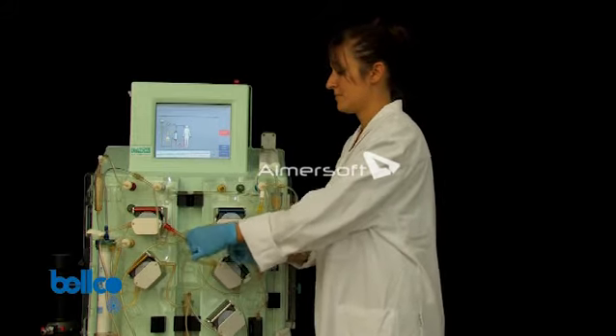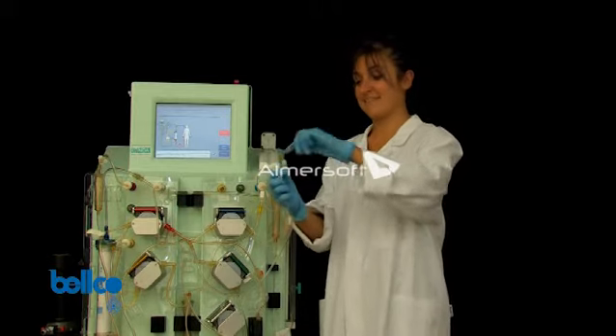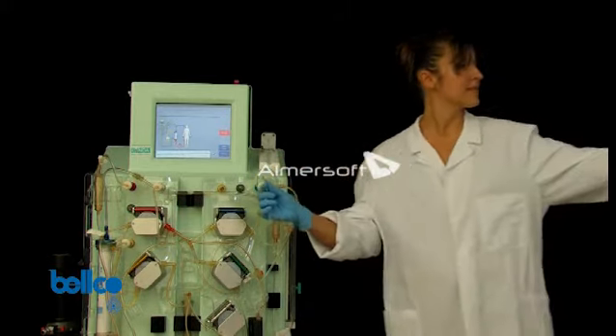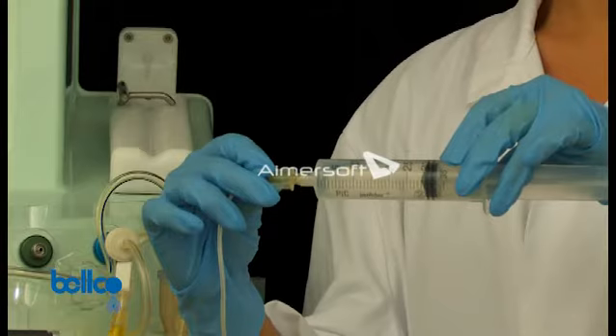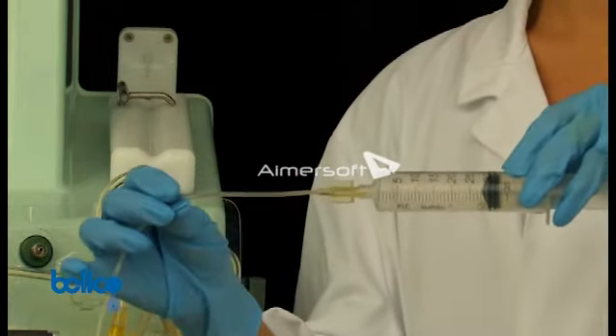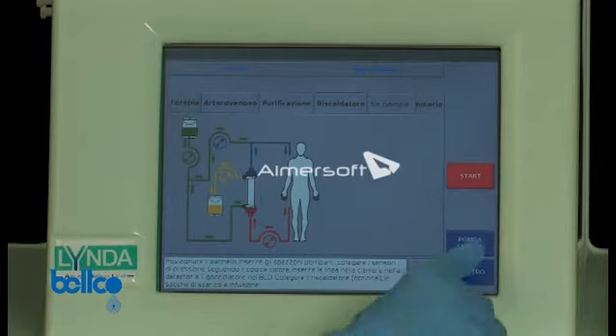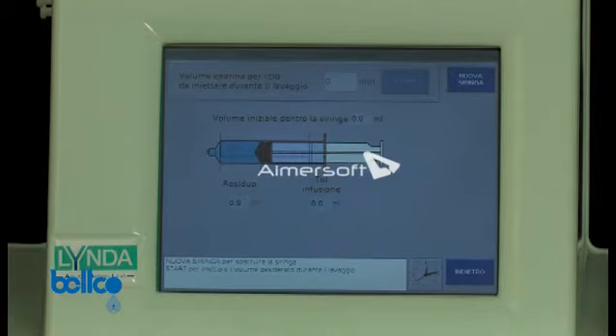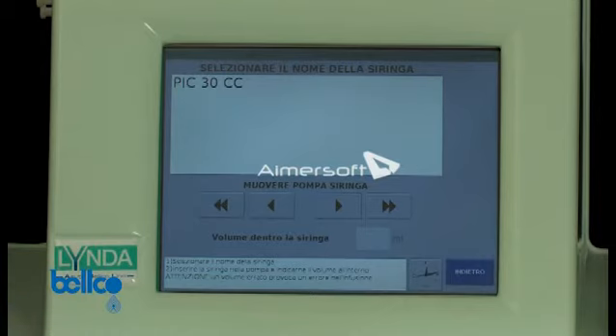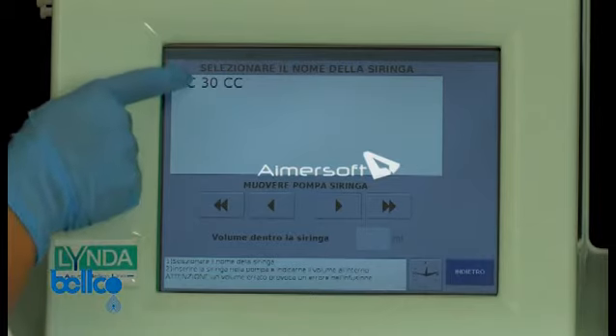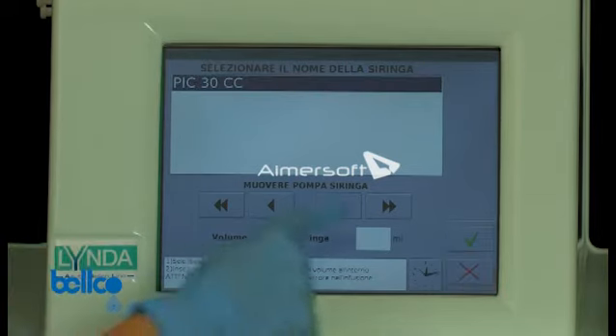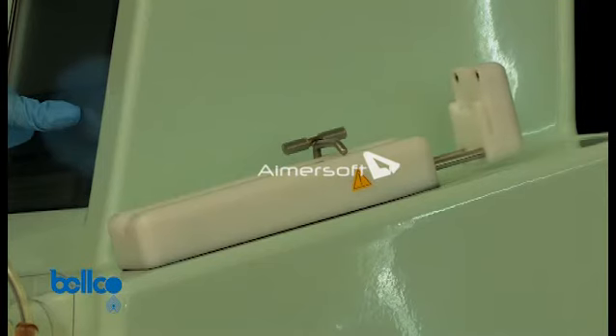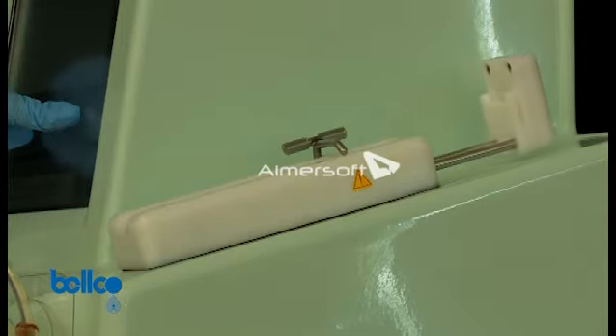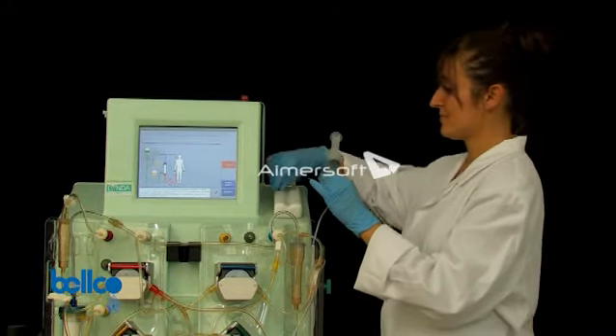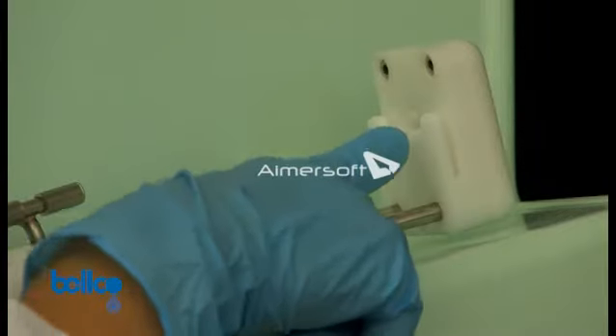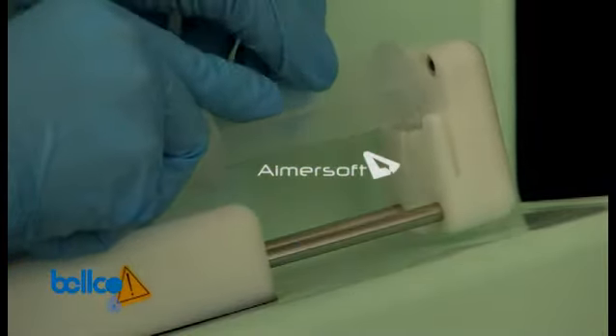Connect the anticoagulation syringe to the dedicated pre-blood pump line. Tap the syringe pump button on the screen and then the new syringe button. Select the syringe type previously set. Move the syringe pump carriage by tapping the arrows as shown on the screen. Accurately and securely fit the syringe into place. Lock the syringe with a dedicated support.